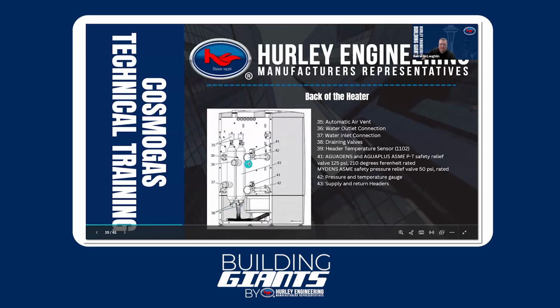Each of these units also has a temperature and pressure gauge on each loop. So each heat exchanger will have its own temperature and pressure gauge, as well as its own T&P relief valve. And that's this item 41 here. So it is a T&P. And for those of you that require pressure only reliefs, then that would have to be done separately. A T&P is what comes standard on them. And that's for the water heater version. I'm sorry, the boiler version would have a pressure only relief.